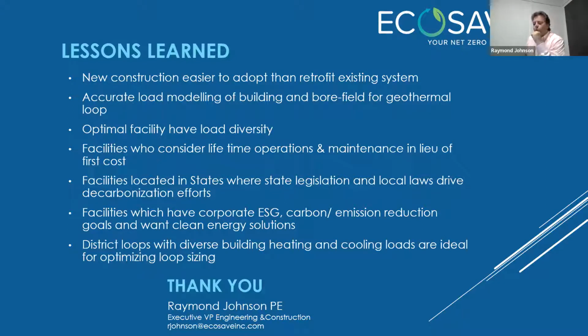For optimal facilities with load diversity, it's much better not to use the bore field purely as a heat sink or source, but to transfer heat to other places. If we're cooling in one area and heating in another, that's beneficial to everyone. Having different use groups on the same bore field is wonderful, though that happens less than 10% of the time when we're transferring heat into or out of the bore field. What we want is to balance it annually so there's no creep in bore field temperature year after year, making sure we reject as much heat out of the bore field as we put into it.